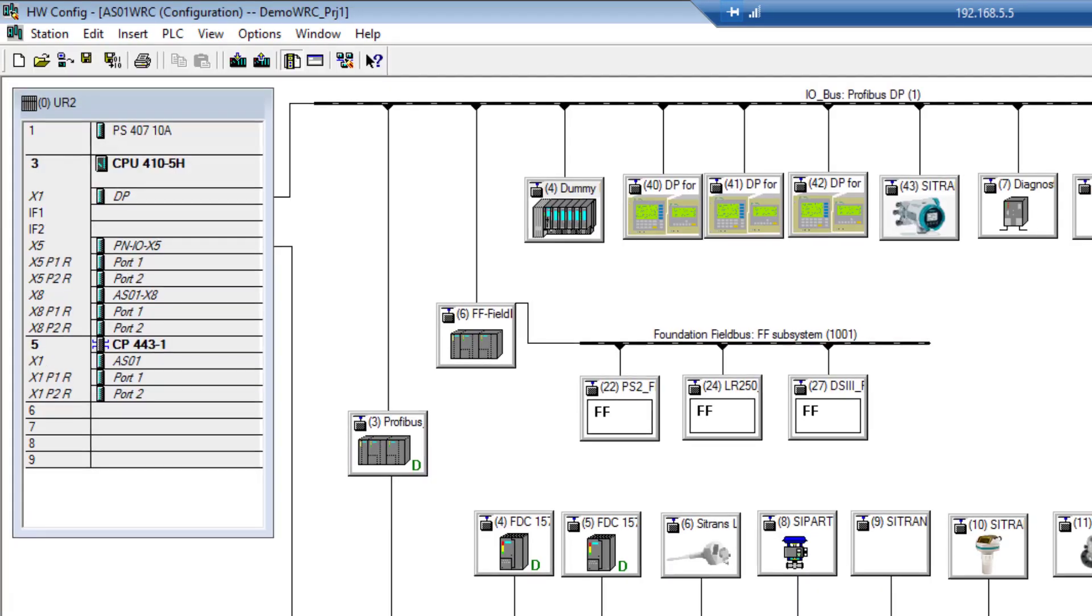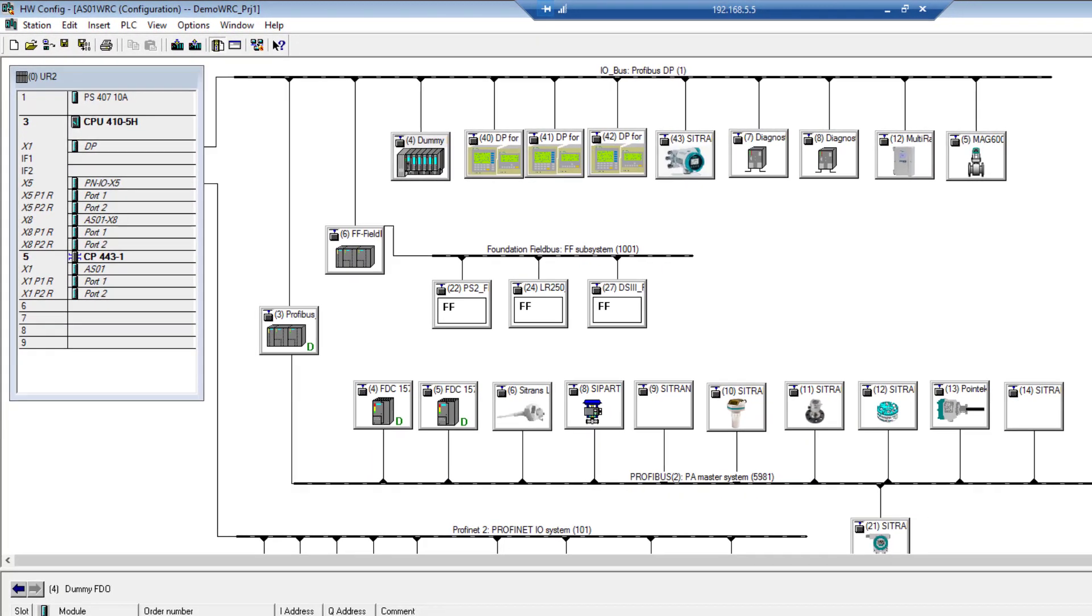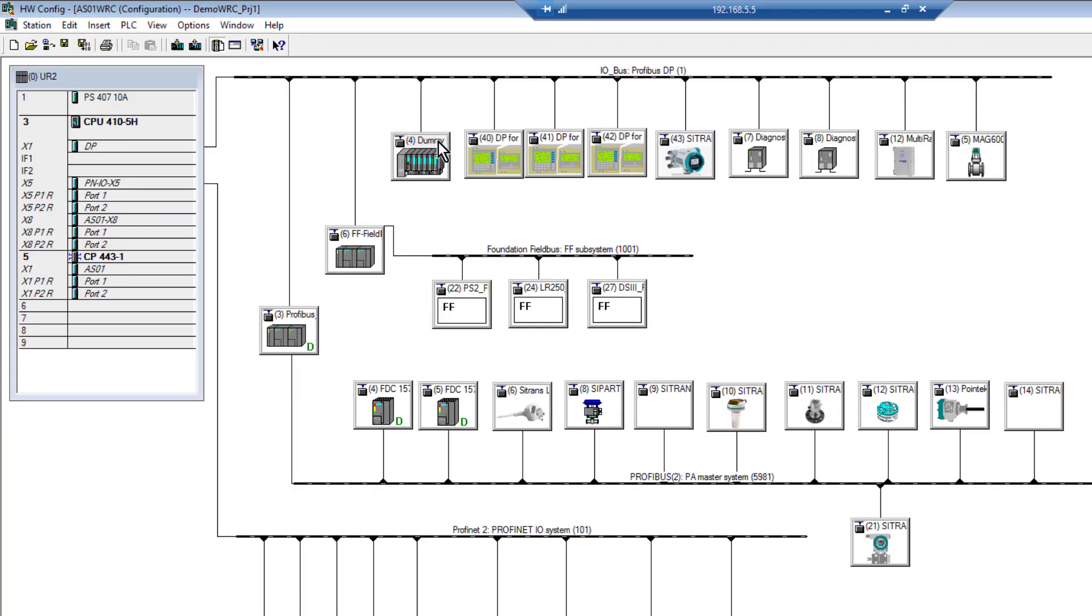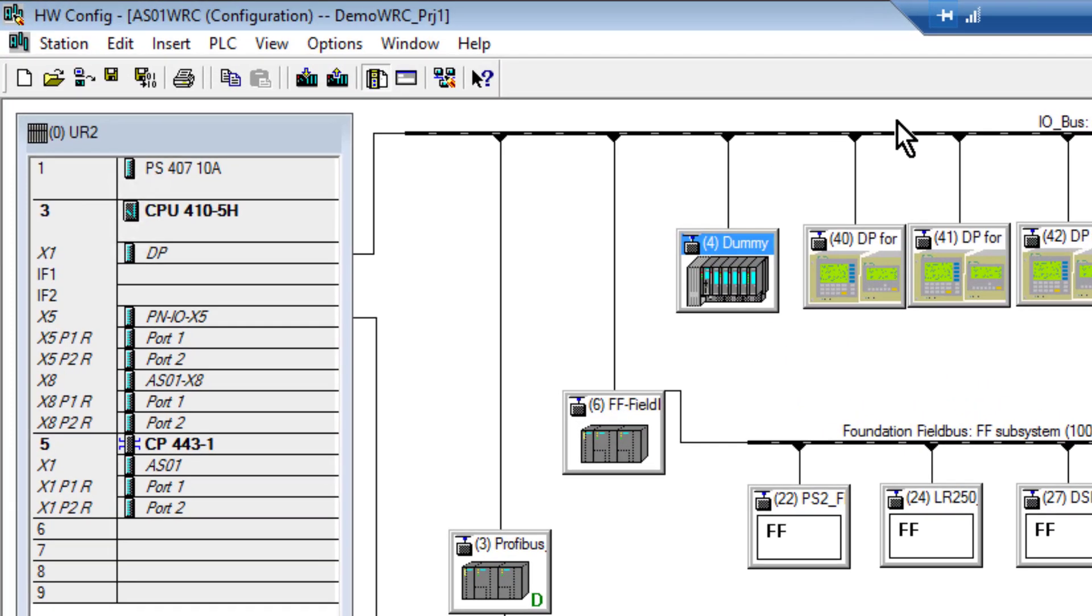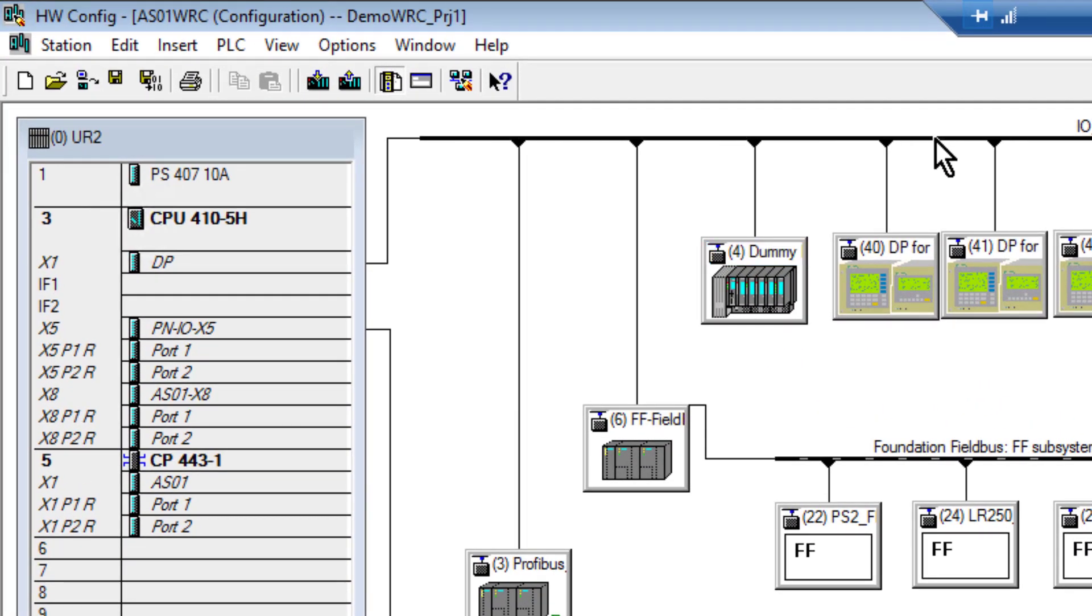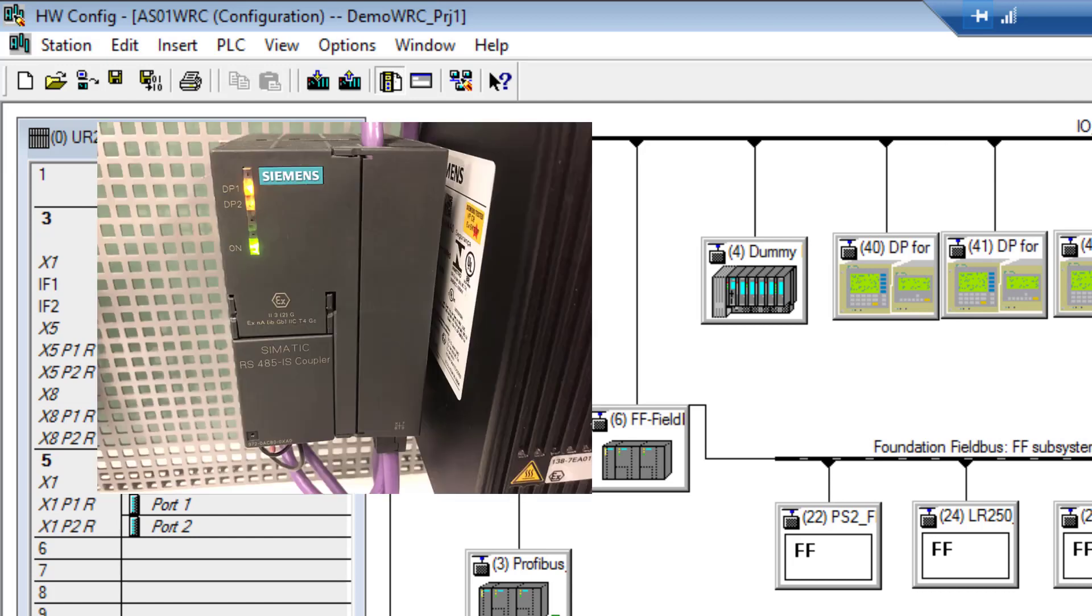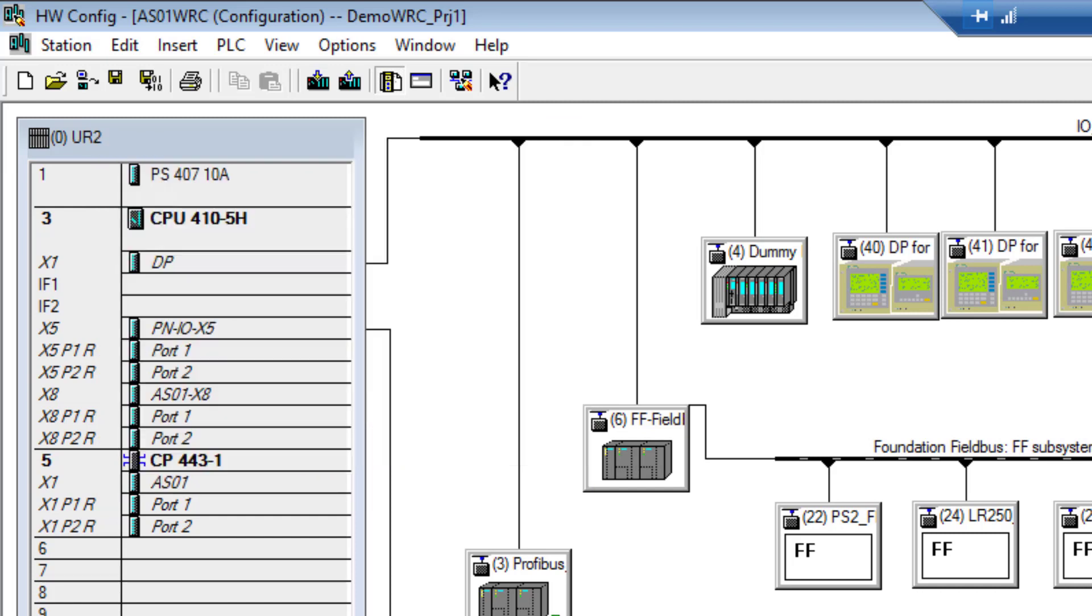Here's my project. I'm connected to our demo room remotely. If I open the hardware screen, I can see my network. The ET200iSP is on my Profibus DP network. You'll have an RS485 intrinsically safe converter in a safe area that converts Profibus DP into something suitable for zone 2, which you can then take into the ET200iSP intrinsically safe cabinet.